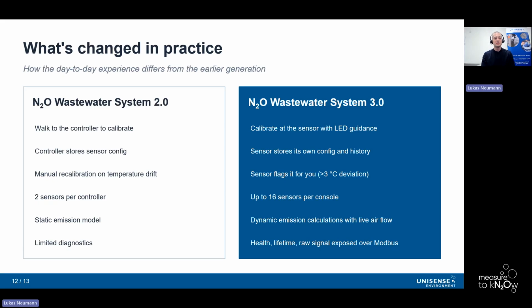Then if we really look at the previous gen with the new generation side by side, previously for calibration, this was done only on the controller, and it could be that this would be up to 100 meters away from the actual sensor placement. So today, you're able to calibrate directly at the sensor without a screen. In terms of configuration, this was previously stored on the controller, meaning you had to calibrate when a sensor was moved, whereas now this is happening straight on the sensor itself. In terms of capacities, this is where we've seen a lot of growth. Now you can connect up to 16 sensors on one console as opposed to the 2 previously.